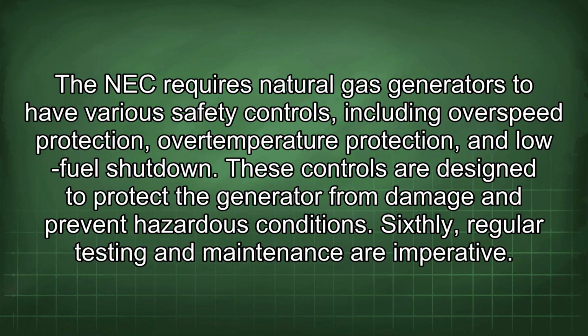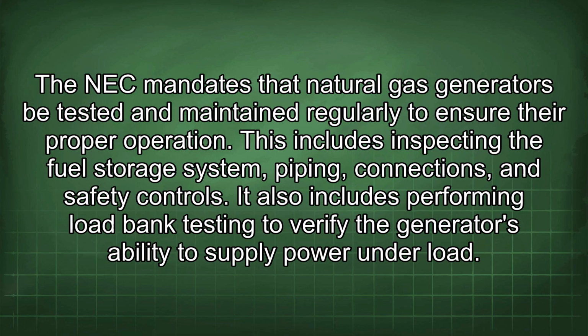Sixthly, regular testing and maintenance are imperative. The NEC mandates that natural gas generators be tested and maintained regularly to ensure their proper operation. This includes inspecting the fuel storage system, piping, connections, and safety controls. It also includes performing load bank testing to verify the generator's ability to supply power under load.